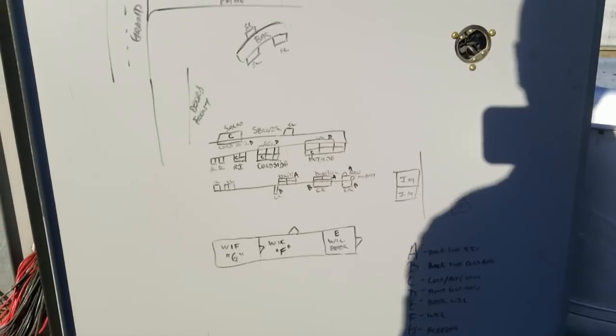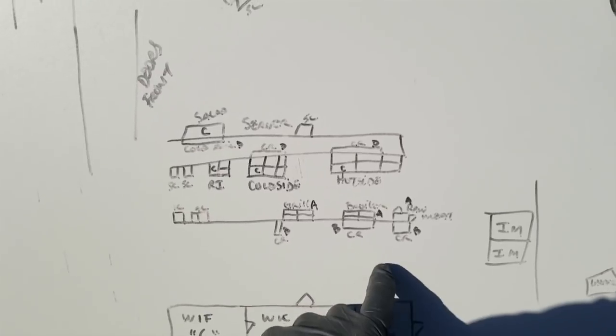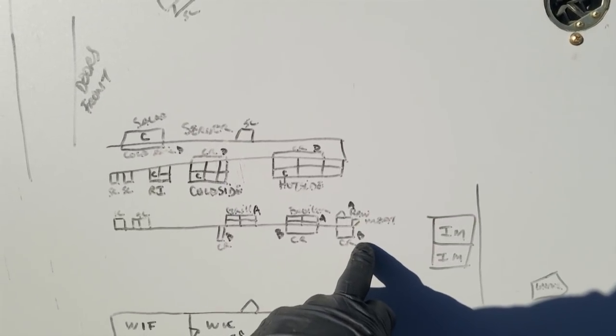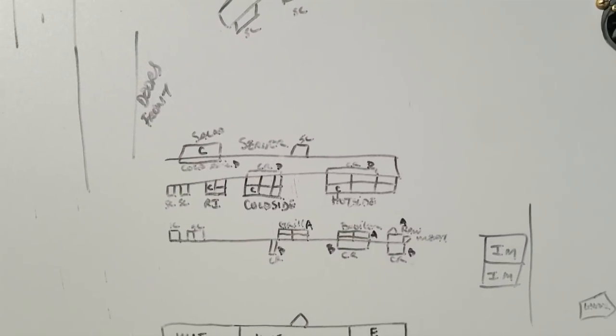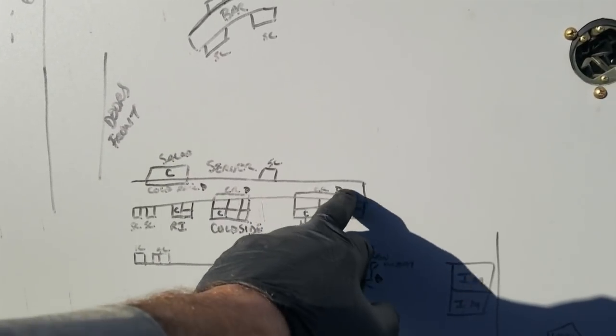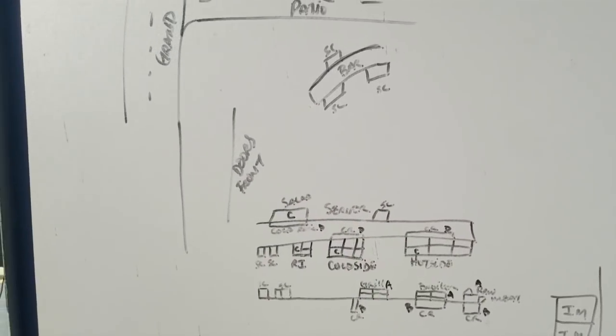I pulled the panels off the rack. In this situation, because we don't know what is what, there's usually a legend. We typically have a legend that somewhat makes sense. Looking at the labels here, someone's labeled CR, CR, CR — so System B controls cold rail, cold rail, cold rail. That's actually on the cook's line, so that's not the one we're working on. This right here is the service station: cold rail System D, cold rail System D, cold rail System D. The three they're complaining about — the salad station, the cold side, and the hot side cold rail — that's all System D.